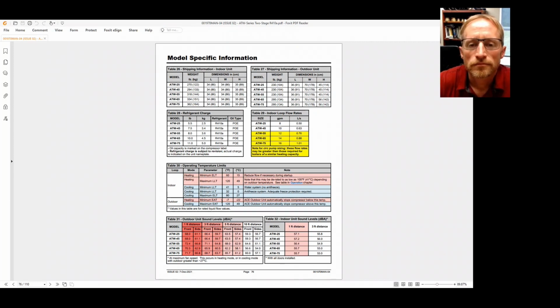Why would you, if you wanted to go instead of 7 degrees down to 4 degrees or 3 degrees, is it just because you could have temperature differentials where some areas could freeze? Oh, definitely. Yeah, it's to avoid freezing for sure, because the temperature inside the heat exchanger of the heat pump is much lower than the water temperature coming out of the heat pump. So the place it's going to freeze is inside the heat exchanger.